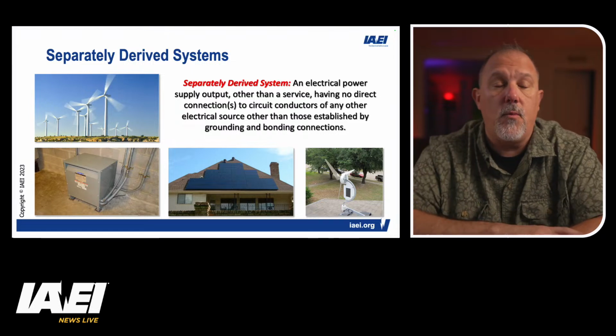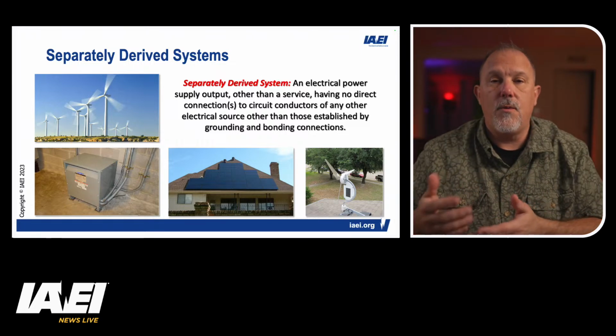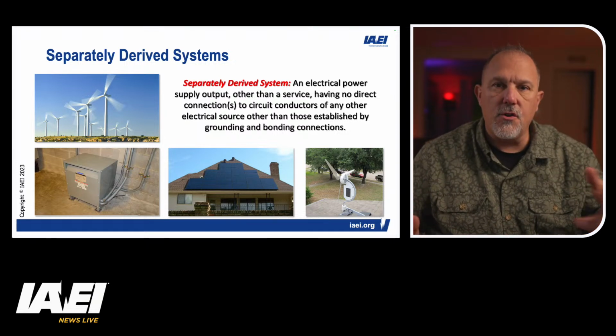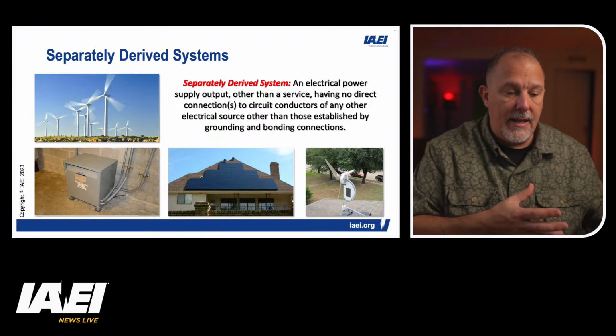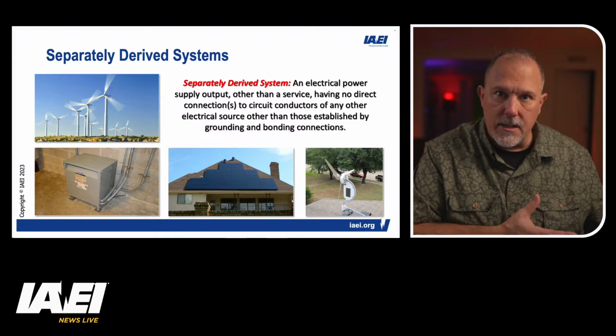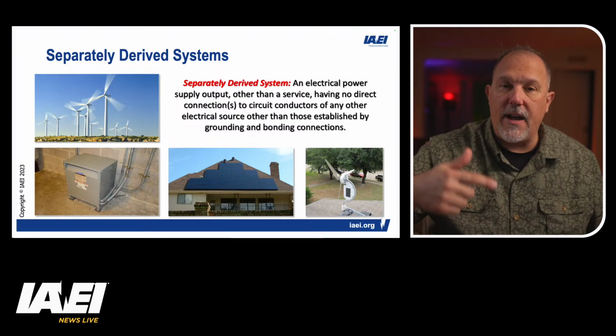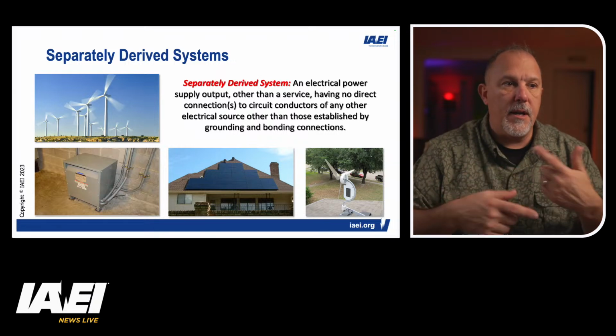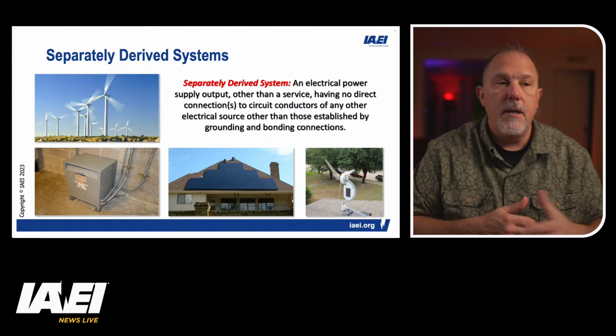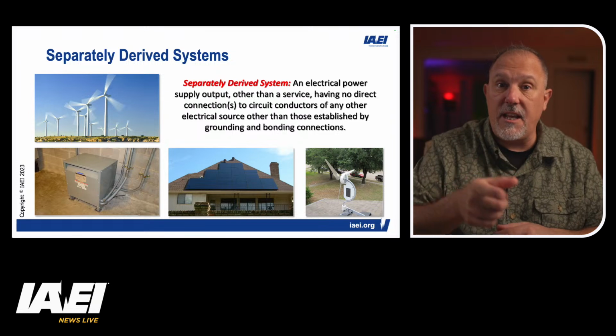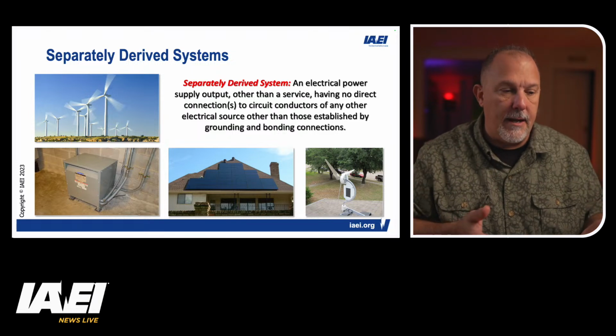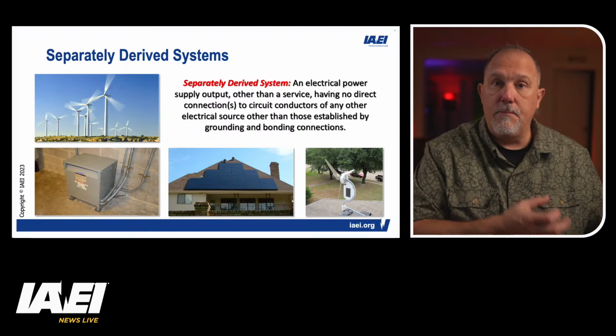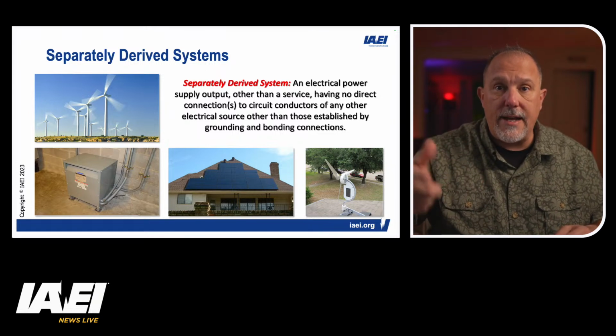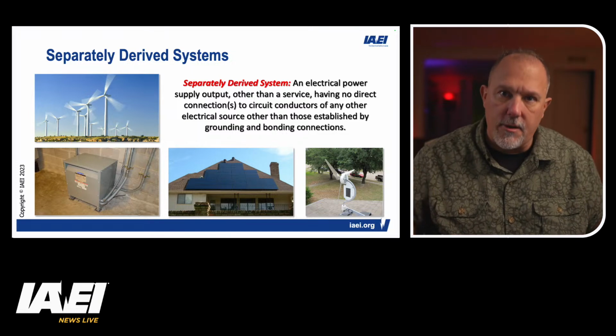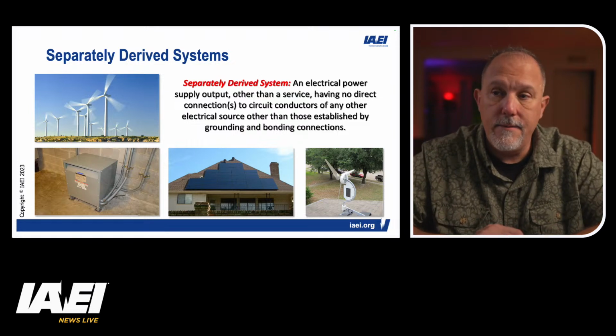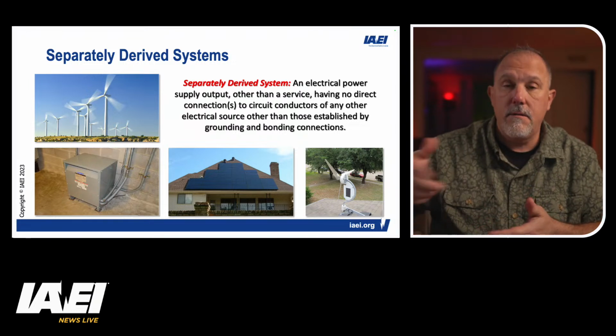You think about a wind system, it's basically a turbine. Talk about wind generation. I'm basically turning the rotor with wind instead of a gasoline engine or a diesel engine or water. Right, so if I had a generator that I'm turning that rotor because of Niagara Falls or something of that nature, or I have a dam and I'm pushing water through a turbine, or maybe steam. There are various ways to create steam. I could use a gas furnace, I can have some sort of boiler where I boil water, create steam, and then I push the steam through a turbine, turn that, and it turns the rotor on a generator, and then I'm generating power. All of those are generators. The prime mover is different. And wind, I mean, come on. It's wind turning the rotor of a generator.